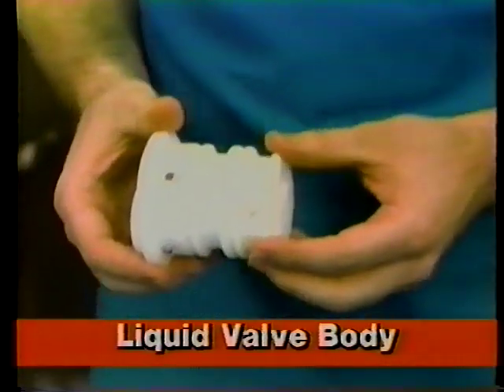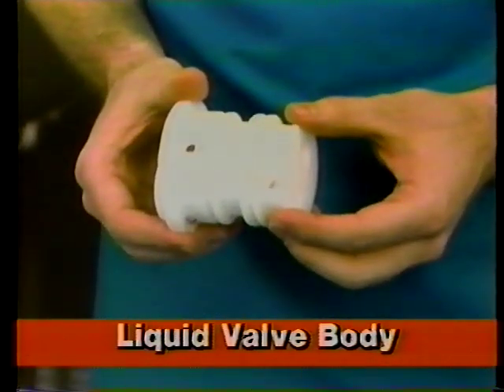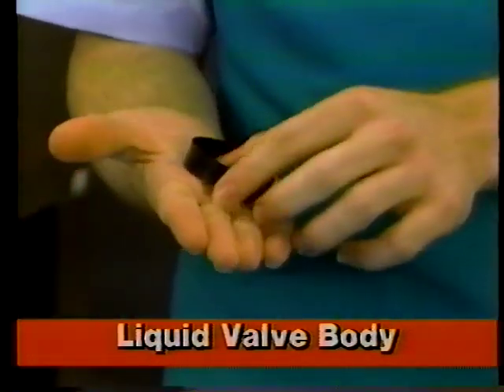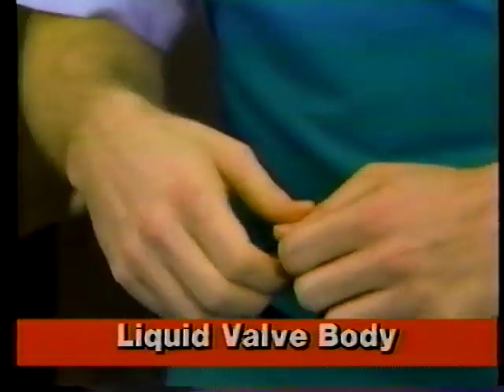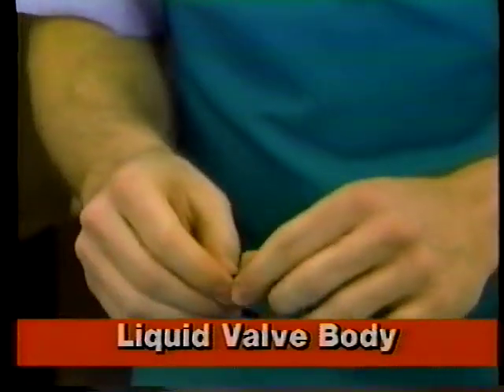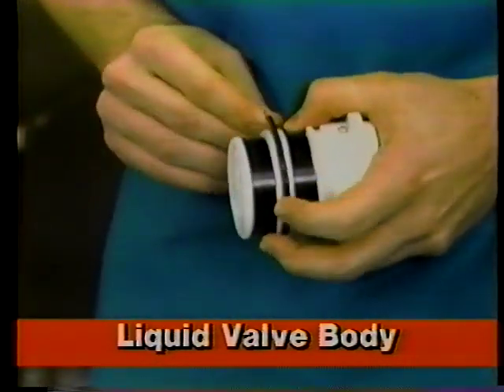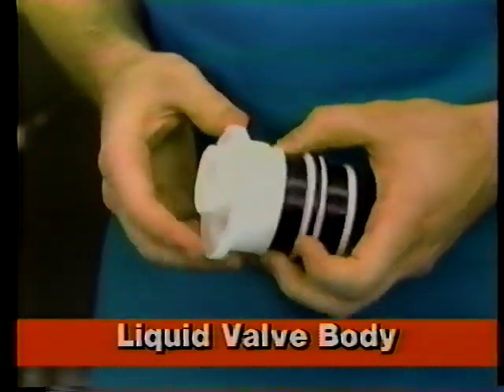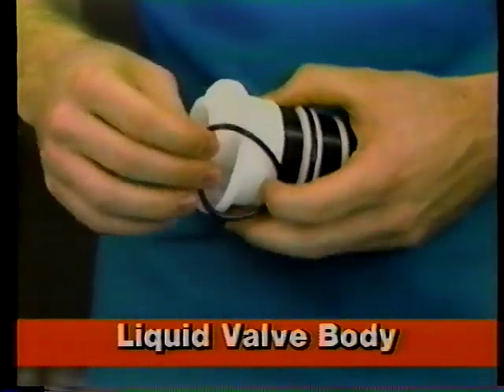The liquid valve body takes 2 O-rings in these 2 grooves and 2 check bands in these 2 wide grooves. Look carefully at the O-rings and bands to make sure they're not damaged. And also, make sure the check bands are flat side out and curved side in. Then slip them all in place. The last O-ring is easier to install if you put it over the other end.